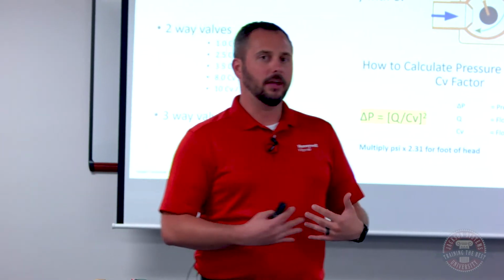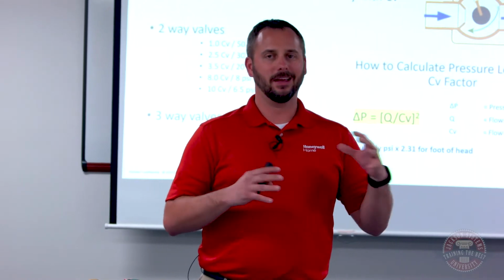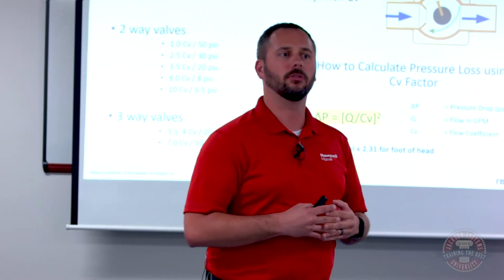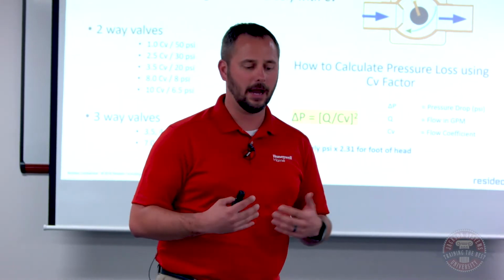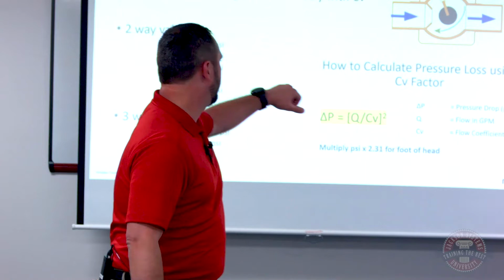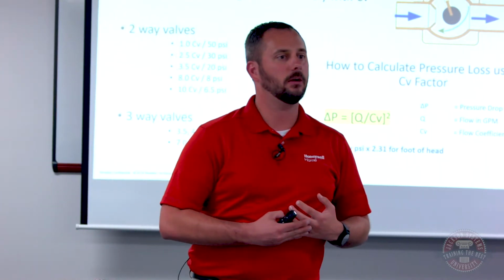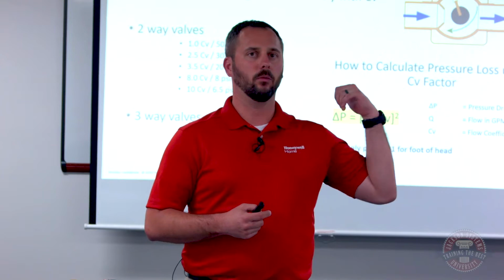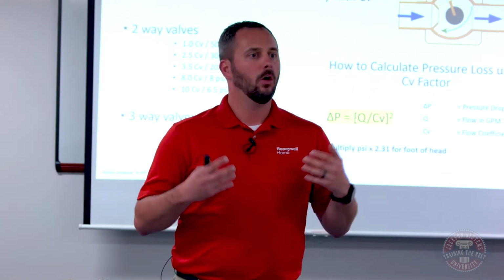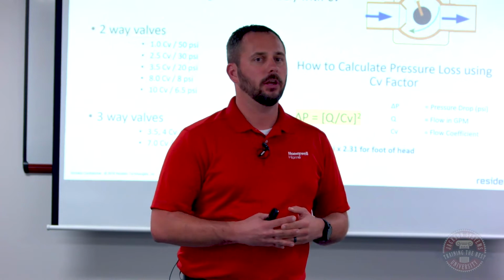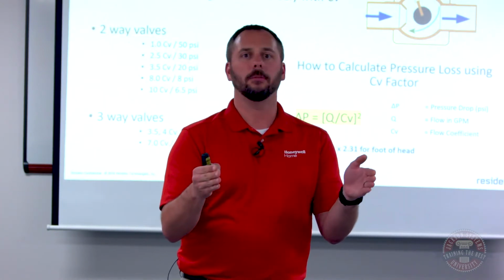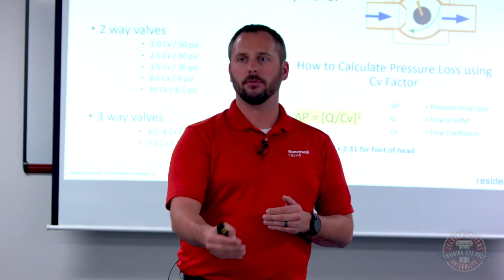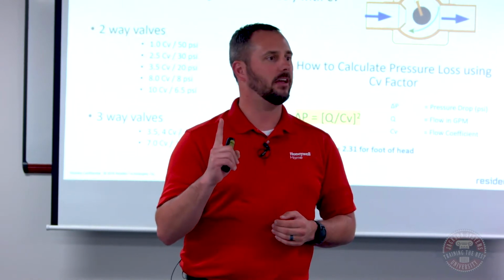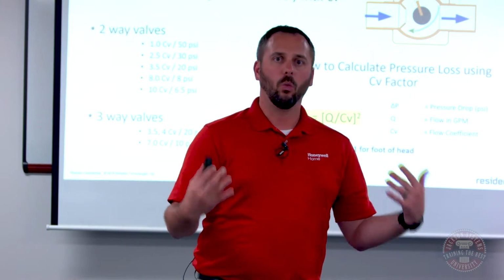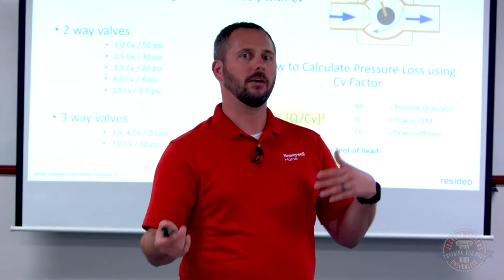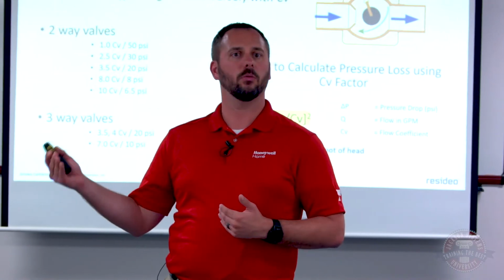When you're looking at pipe sizing and zone valve sizing, this doesn't necessarily make or break it based on pipe size. If you've got a 1 1/4 inch because you need to deliver 10 gallons a minute, you see down there I have a couple of valves that are listed between 8 and 10 CV. I've got some 1 inch valves with a CV rating of 8. What CV means in a nutshell is, if I have a CV rating of 8 and I'm driving 8 gallons a minute through that valve, I will have 1 PSI of pressure loss. Remember that formula I gave you earlier: 1 PSI of pressure loss is equal to 2.31 feet of head.